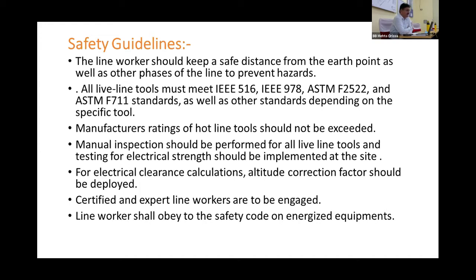The manufacturer's rating of the hotline tool should not be exceeded. A manual inspection should be performed on all live line tools, and electrical strength testing should be implemented at site. For electrical clearance calculation, the altitude correction factor should be applied, since if the contour of the land differs, the minimum available distance must be factored in properly.